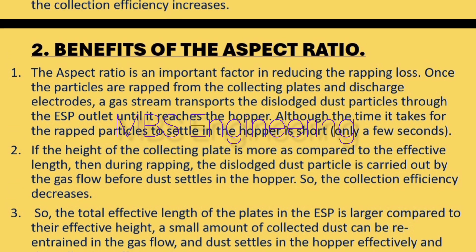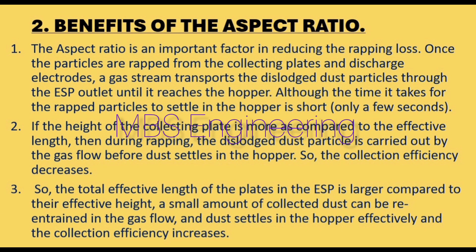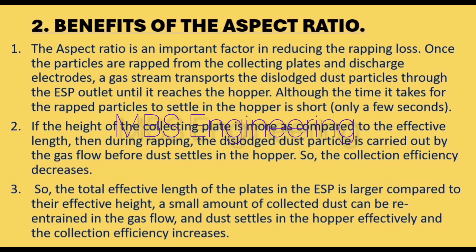Point 2: If the height of the collecting plate is greater compared to the effective length, then during rapping, the dislodged dust particle is carried out by the gas flow before it settles in the dust hopper, so the collection efficiency decreases. Point 3: So, if the total effective length of the plates in the ESP is larger compared to their effective height, a small amount of collected dust is re-entrained and the dust settles in the hopper effectively, increasing collection efficiency.